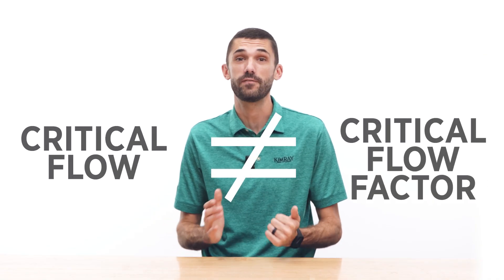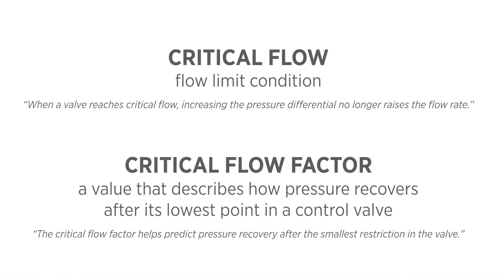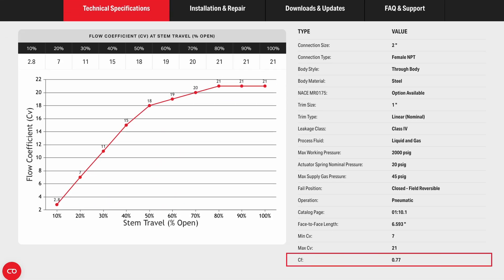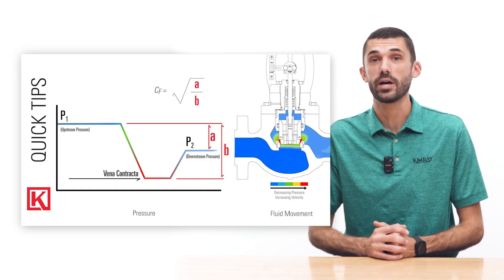One last note: critical flow is not the same as critical flow factor. Critical flow is the flow limit condition, while critical flow factor is a value that describes how pressure recovers after its lowest point in a control valve. CF is used in flow calculations and is listed on each product's detail page. For more on critical flow factor, check out our video and blog. Reach out to Kimray support if you have concerns or questions about how critical flow can affect your valve sizing.